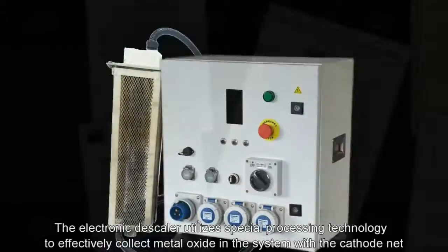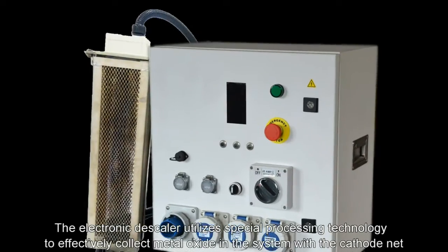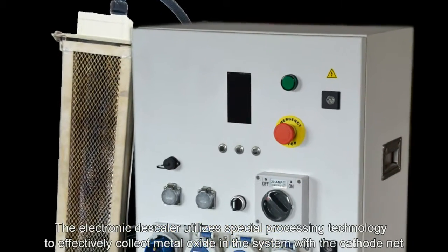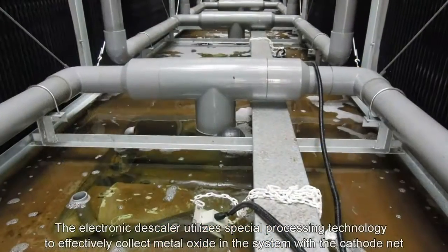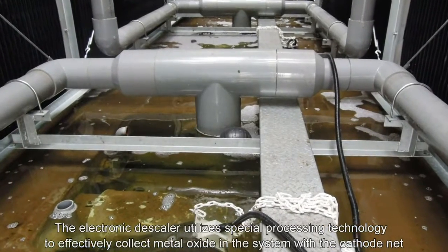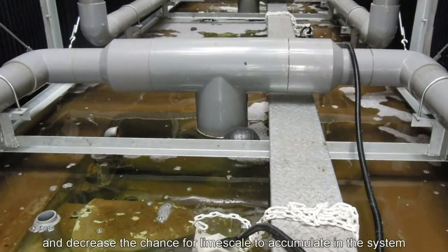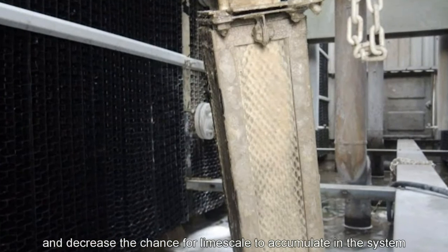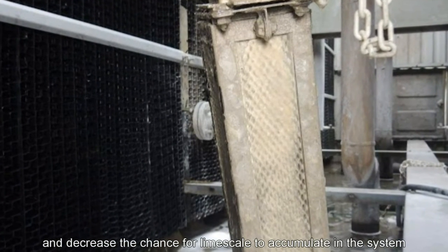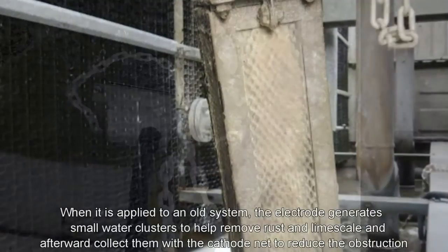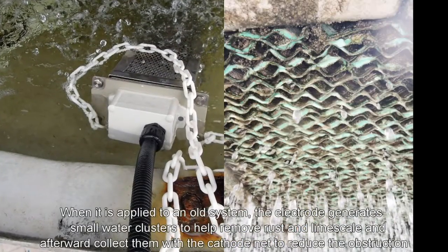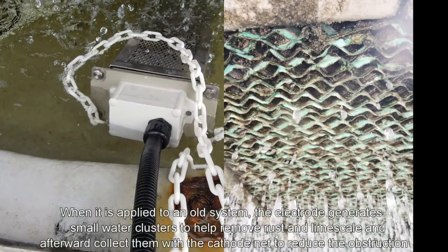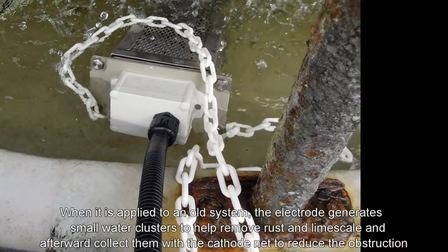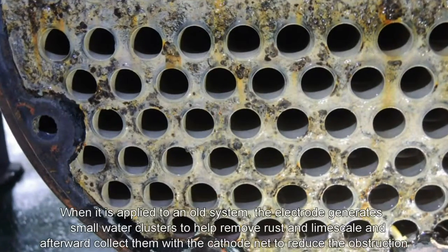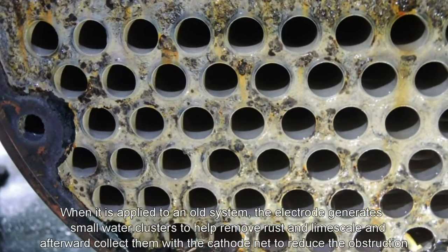The electronic descaler utilizes special processing technology to effectively collect metal oxide in the system with the cathode net and decrease the chance for limescale to accumulate in the system. When it is applied to an old system, the electrode generates small water clusters to help remove the rust and limescale, and afterward collect them with the cathode net to reduce the obstruction.